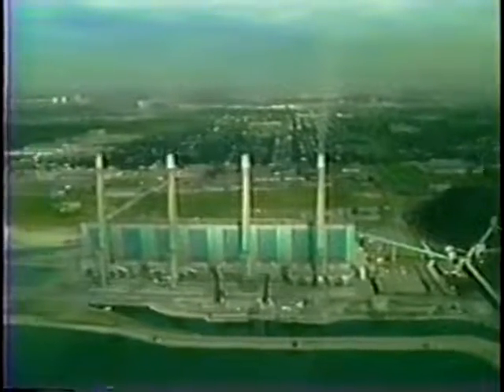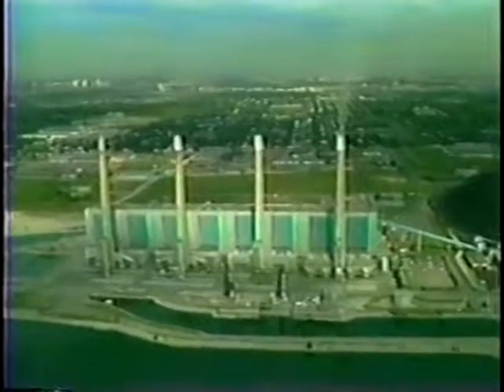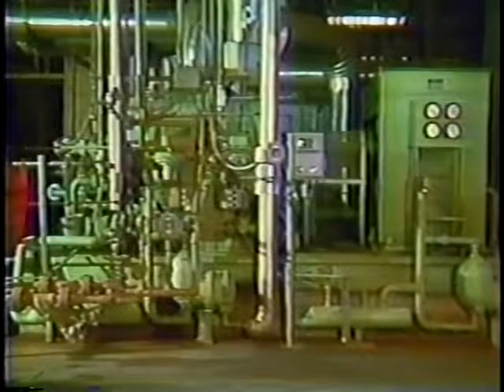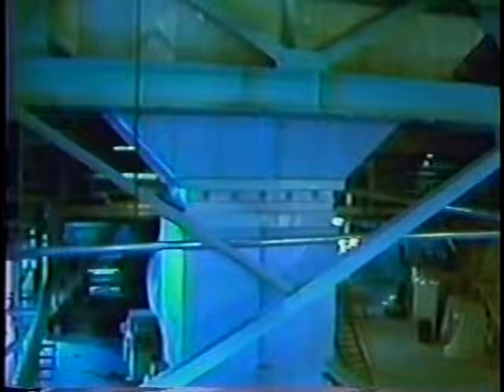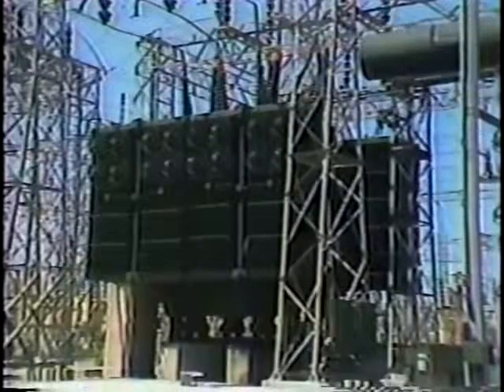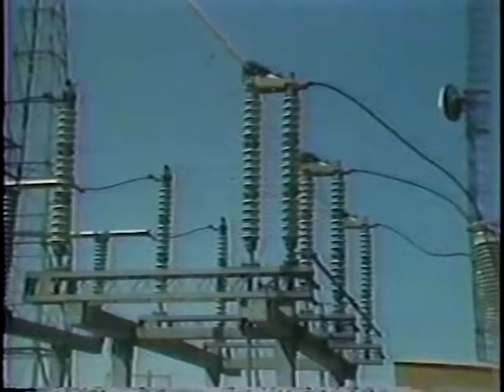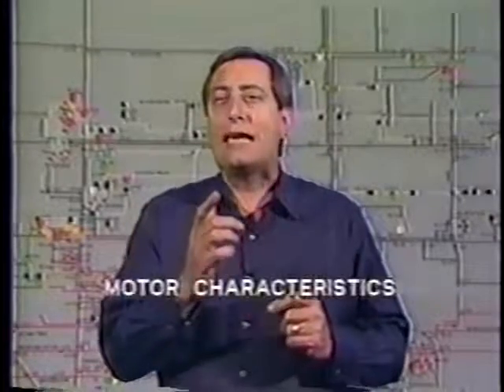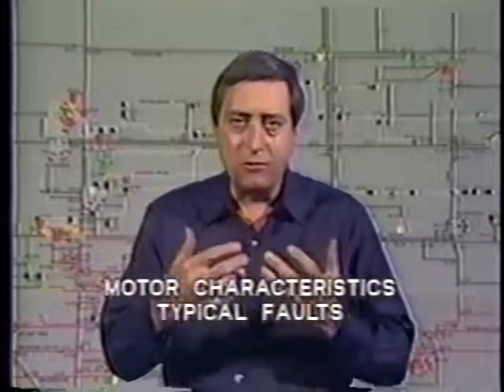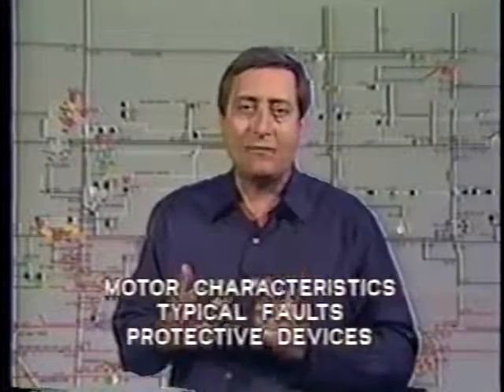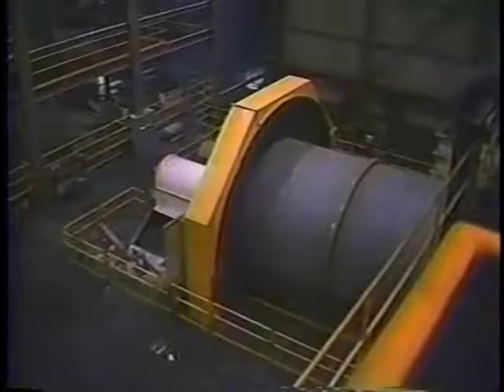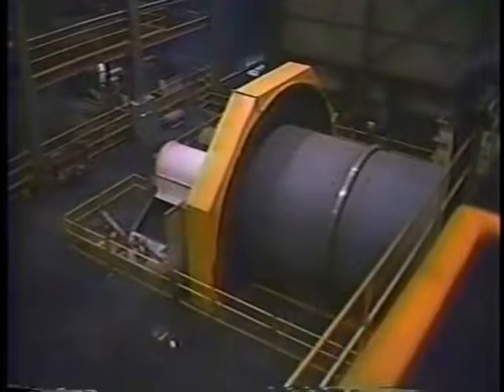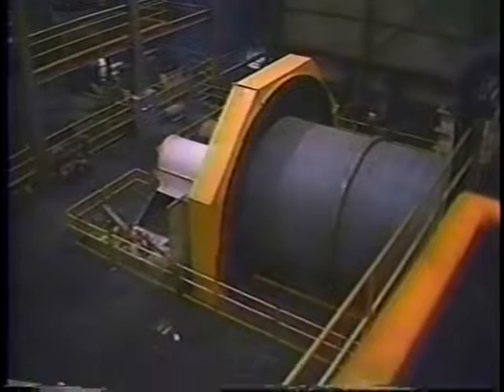In the electric power industry, motors have widespread application, particularly in power stations, where they drive boiler feed pumps, boiler fans, and a multitude of other equipment. In the substation, motors will drive transformer fans, oil pumps, disconnect switches, and so on. Because of this wide application of motors throughout the power system and also across the whole range of our customers, we need to know the characteristics of electric motors, typical faults which may occur, and the protective devices which are installed. We are particularly interested mainly in the larger motors whose performance may reflect back into the power system.